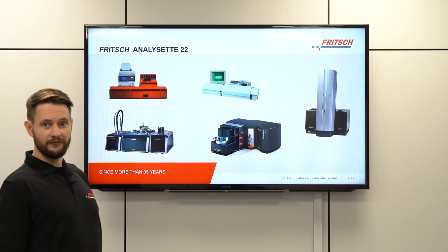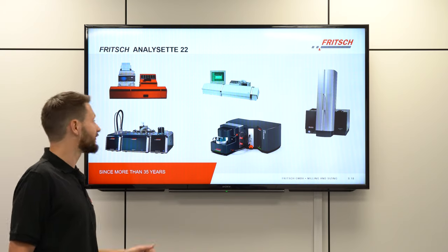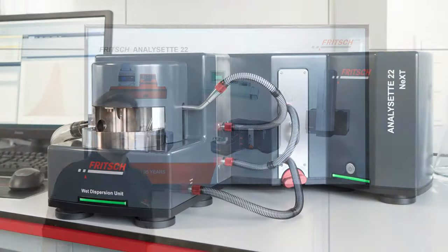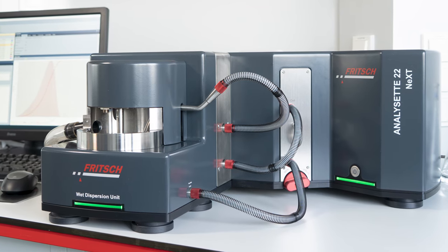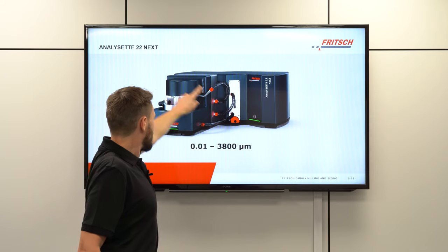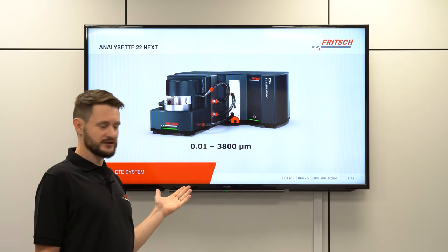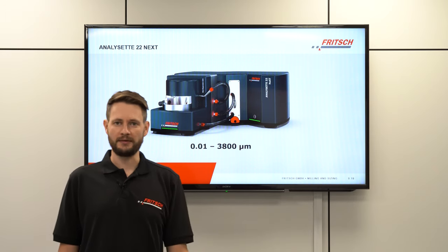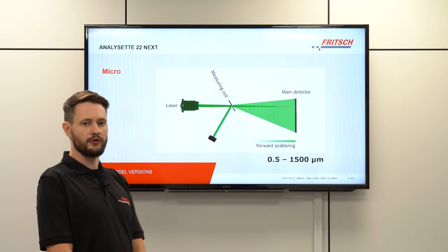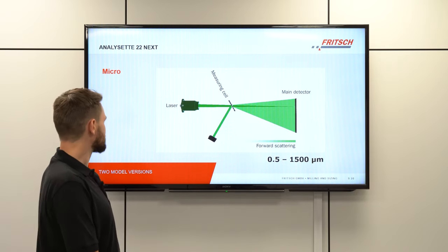Here we see a gallery of the last 35 years of Fritsch laser particle sizers. The first instruments look quite different from today's models, and importantly this is not shown to scale — the newest instrument is by far the most compact one. Looking more closely, you can see the wet dispersion unit in front and the separate ultrasonic box at the back. The full system has a measuring range of 10 nanometers to 3.8 millimeters, while a more basic version offers a range of 500 nanometers to 1.5 millimeters.